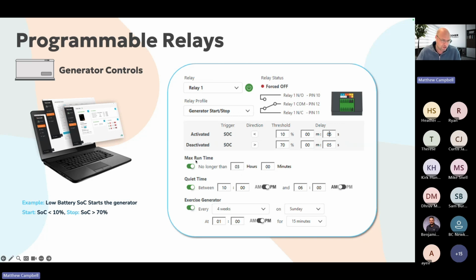The other thing you can do is set a maximum runtime, which you can toggle on or off. It comes defaulted off, but you can set run the generator for no longer than a number of hours and minutes, which would override this. So if you hadn't reached 70% SOC by the time 3 hours had elapsed, it would shut off. And I'll talk about a scenario where this comes in handy in a second.